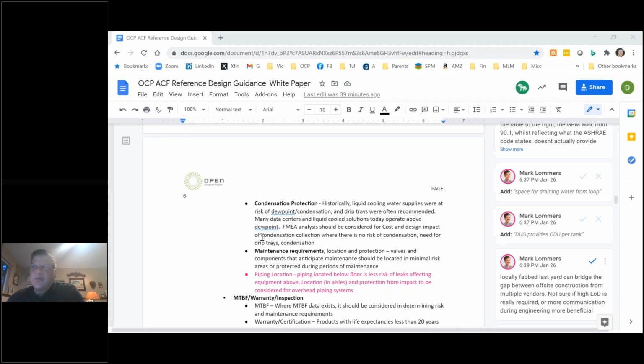So one of the questions that we definitely need to look at is, if you're adding pipe or a liquid loop into a data center, you have several options. One option is that you maintain the temperature of your pipe above dew point. Another is that if you can't guarantee the temperature of your pipe above dew point, you put in some sort of protection to make sure you don't have condensation, or if you do have condensation, you're aware of it and you're draining it and it's not causing corrosion. I'd like to have someone else jump in here. I know John Gross, you're online. Can you clarify the concerns I have here and maybe share them with others?